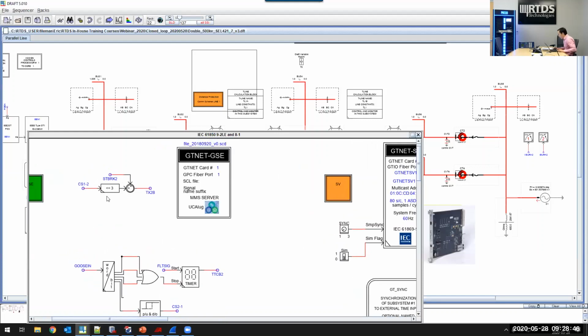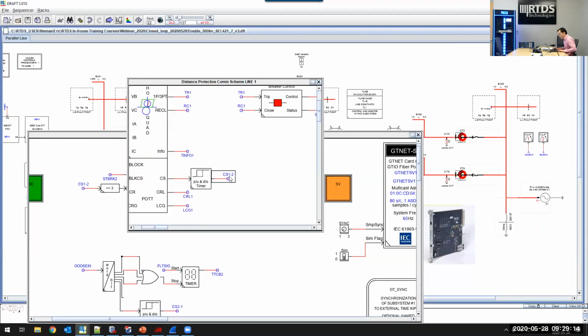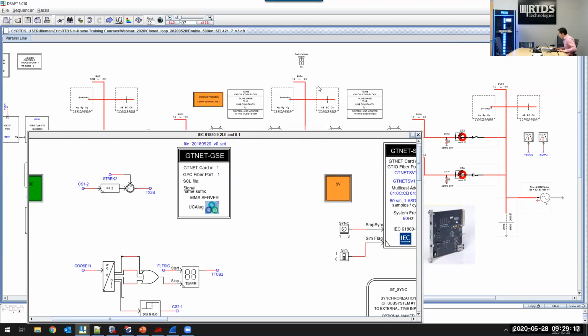Now, the simple logic here is to get the parameters that need to be sent to the relay, which include a 3-bit integer STBRK2, which comes from this breaker control component, representing the phase ABC status of breaker 2. And there's a 1-bit extra status from the relay model at the left side terminal, which is here, CS12, which represents a permissive transfer trip signal for the POTT scheme adopted in this demo. The combined output variable TX2B, which contains 4-bit information, will later be associated with the GTNet GOOSE output dataset.